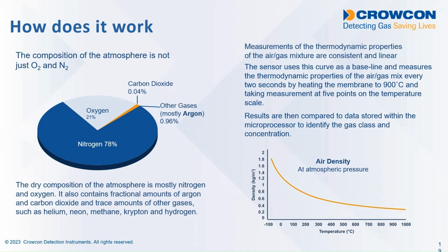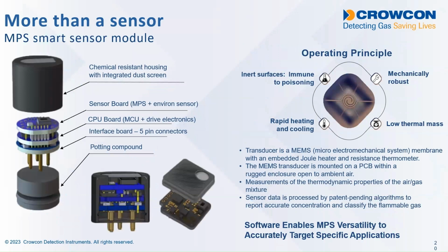And the thermodynamics will change as the mixture of air changes, and that will include the introduction of things like hydrogen and other flammable gases into the air mix. So it's using that air composition as a baseline for its measurement, and any changes are compared to data that's stored in the sensor. So that's what the sensor looks like. It has a tiny transducer. It's a MEMS microelectromechanical system transducer, very, very low mass transducer that can be heated up and cooled down very, very quickly. It also includes a joule heater, which is able to measure the amount of energy that's taken to heat the MEMS sensor up, and then there's a resistance thermometer.